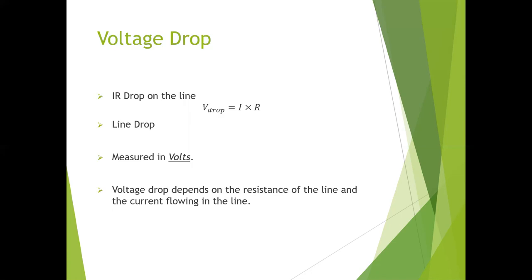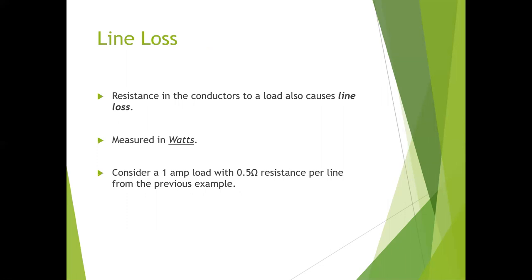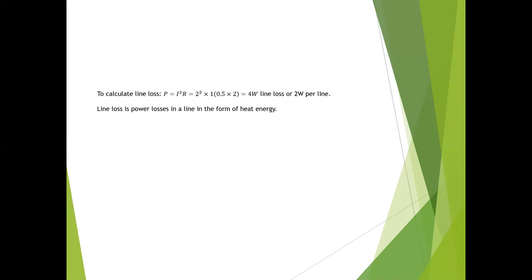We've got our volt drop and that equals I times R. We also call this line drop. Don't confuse that with line loss because some questions will ask you what is the line drop for this resistor or load, and you have to make sure you are not calculating line loss. It is measured in volts and indeed does depend on the resistance of line and current flowing through it. If we consider that previous example with the 0.5 ohm resistance per line, we can actually calculate the line loss using our I squared R formula. We have 4 watts total of line loss or 2 watts per line, and these losses are going to be in the form of heat.